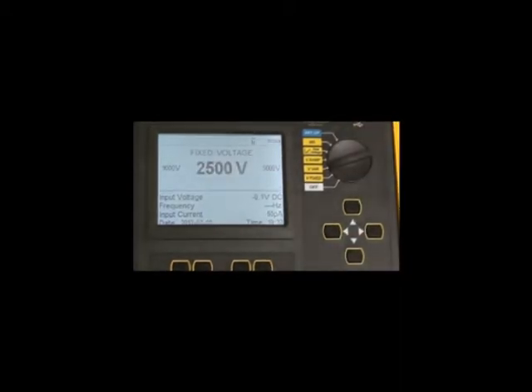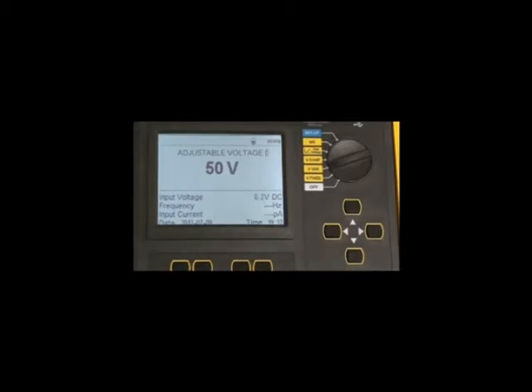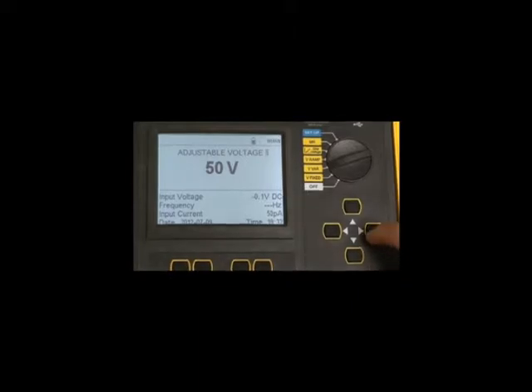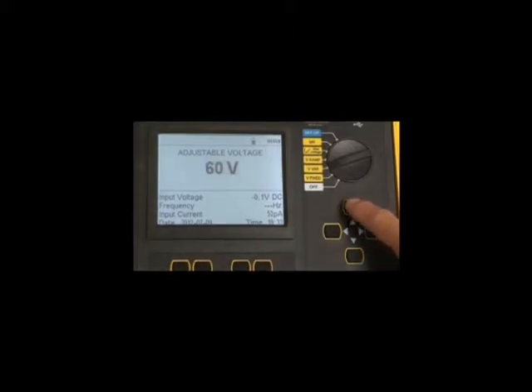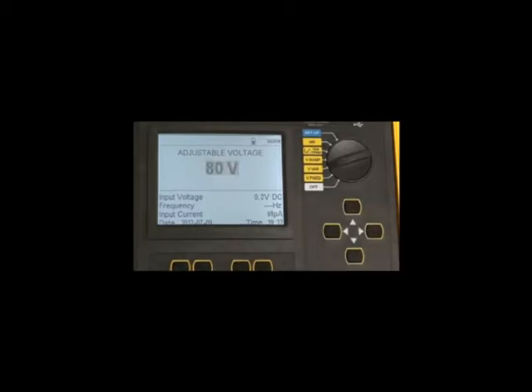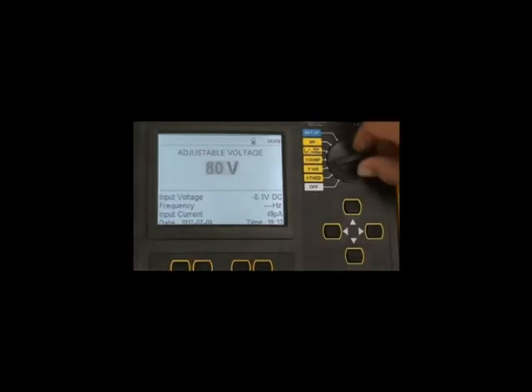In the V ramp position, the user can program a test anywhere from 40 volts to 10 or 15,000 volts by again accessing the specific voltage using the navigation key and then pressing the start button to start a test at that voltage.